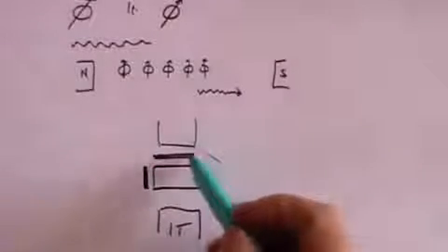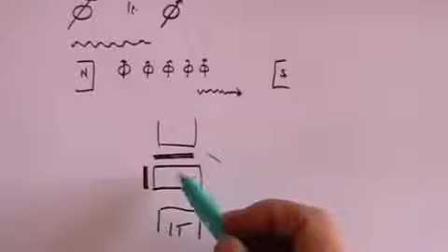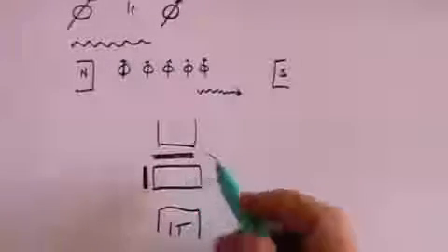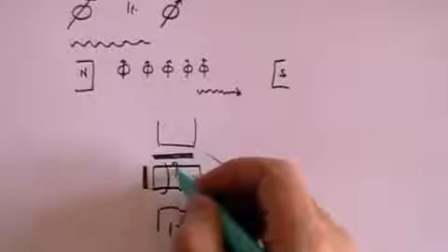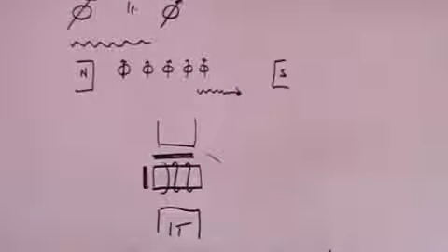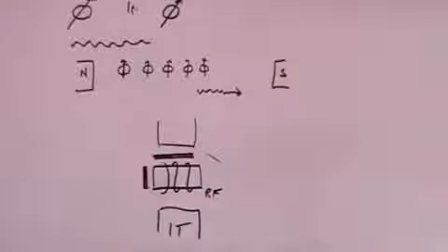You have 2 additional magnets, which produce a non-uniform field. The reason for those is that that will enable you to detect whereabouts in the body you're getting information from. And then around the bed, you have your coil. That coil is going to be the generator of the radio frequency information, and it also will detect radio frequency information.